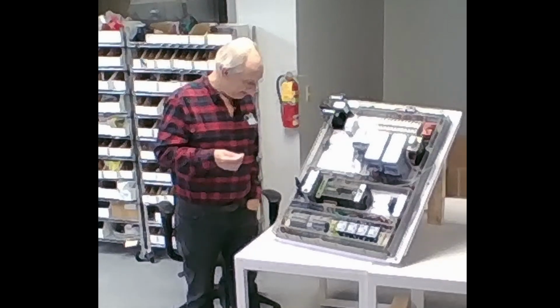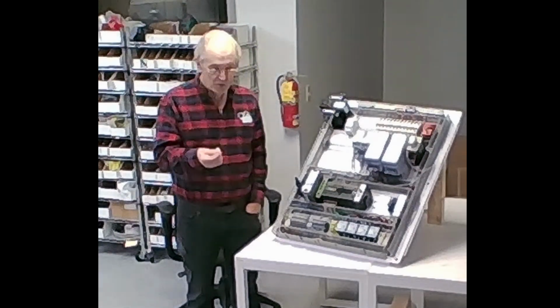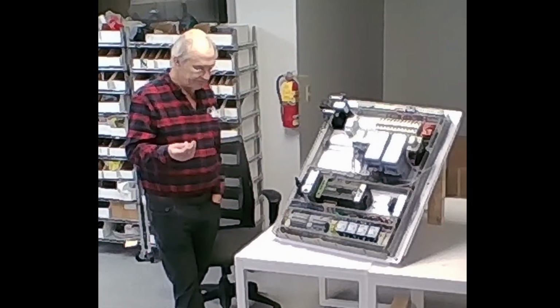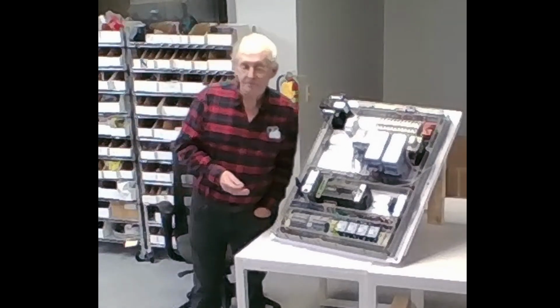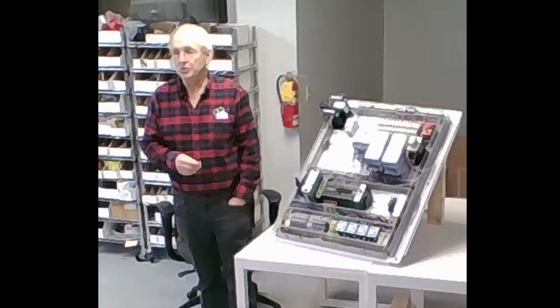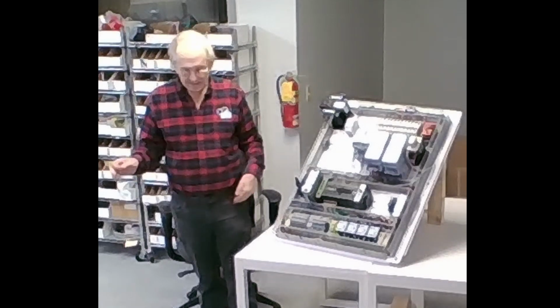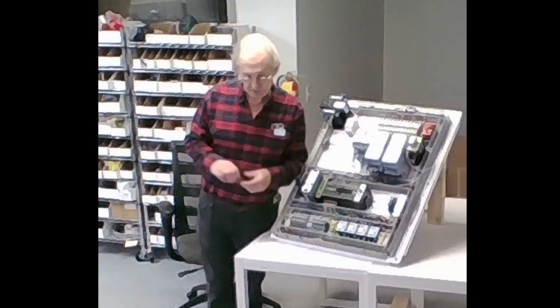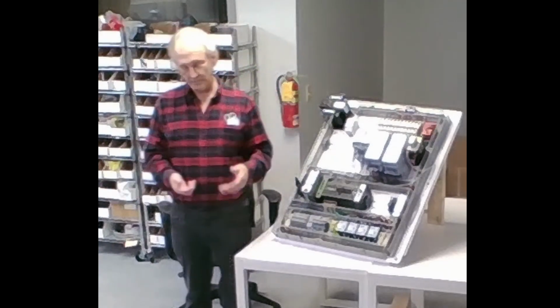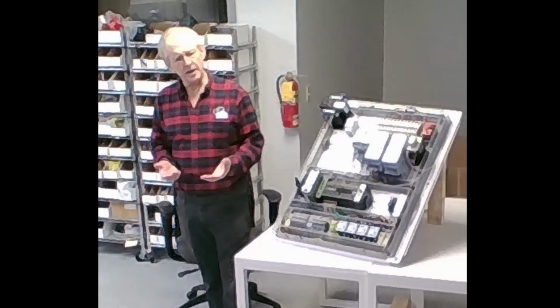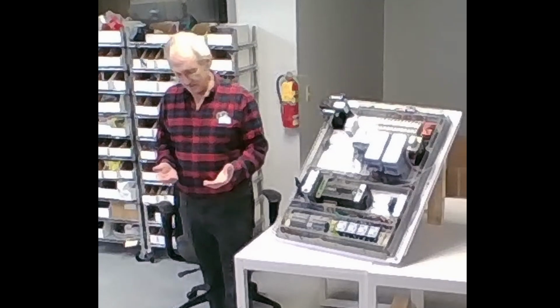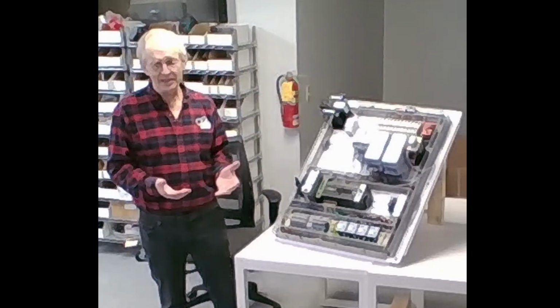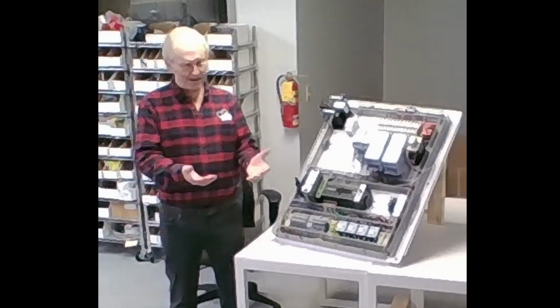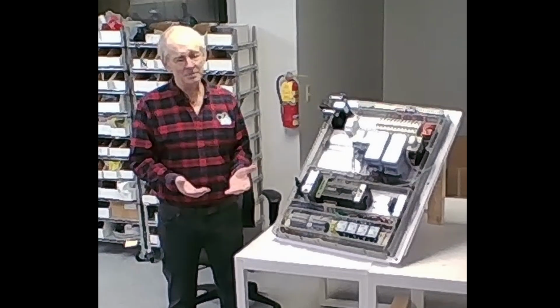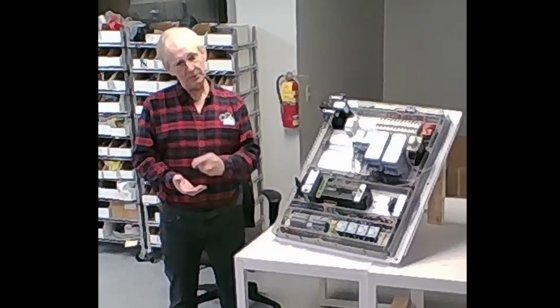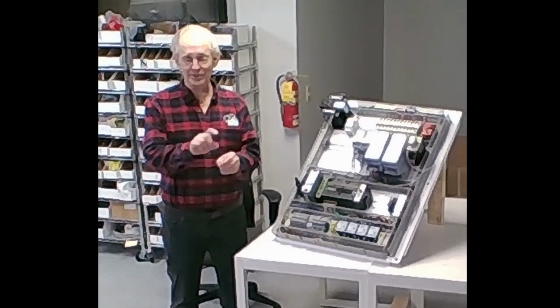Okay, now years ago, in what fuses can tell you, there was a car wash, and the guy had burned out 5 big blowers in a row, and his electrician couldn't find the trouble, so he asked me to come in and check. And he had a pile of fuses laying there, and we looked at everything, and I couldn't find anything wrong. And I see this pile of fuses, and I pick them up, and I said, "Did it blow all the fuses each time the motor went bad?" "Oh yeah." "Oh, I think I know what's wrong." And he's like, "You reading tea leaves?" I said, "Well, kinda. You see, I have 12 fuses here, and there's 3 fuses on each motor. And you notice that 4 of them are slightly blue on one end. They were big copper fuses, right?"